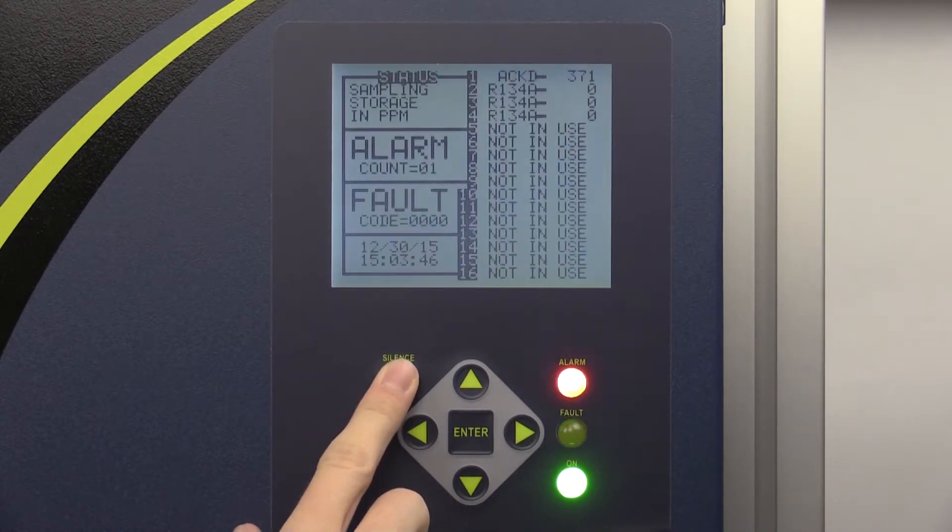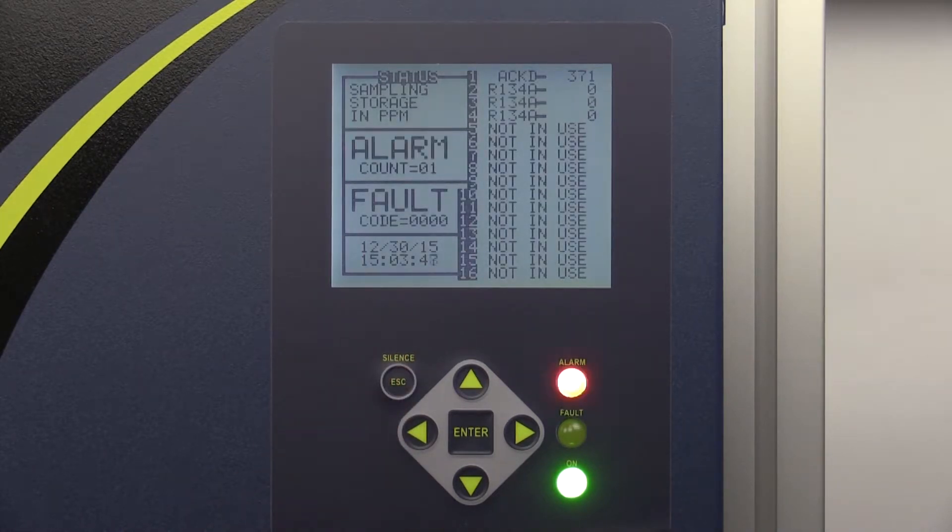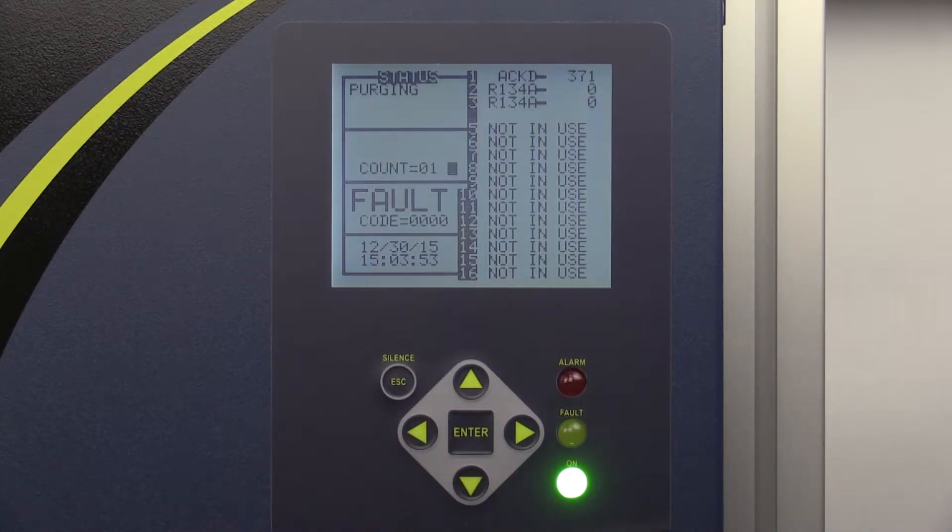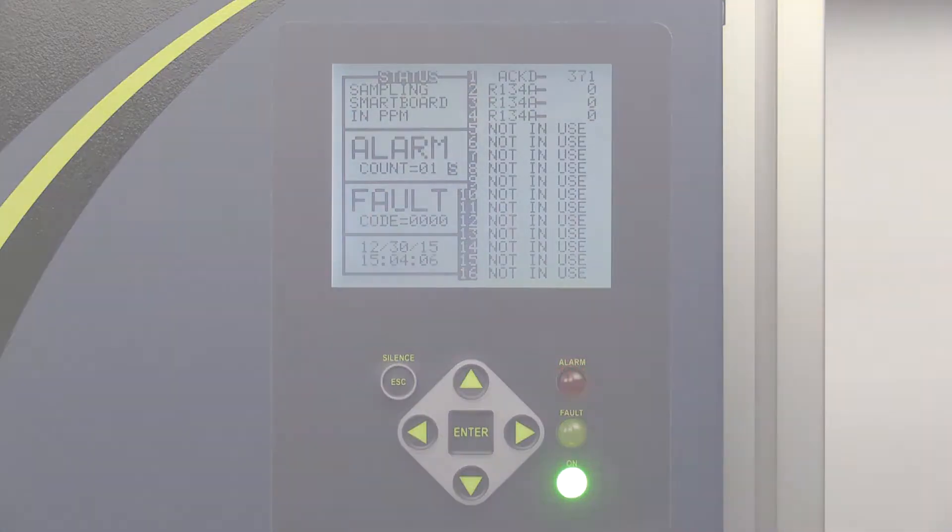Triggered alarms can be silenced by pressing silence and then enter on the main data display. In auto mode, the red alarm light will continue flashing until the PPM reading has fallen back to safety level. In manual mode, the red light will stay flashing until the alarm has been acknowledged and the PPM has reached a safe level.